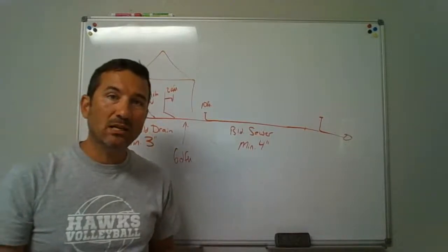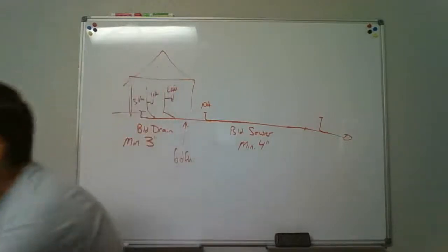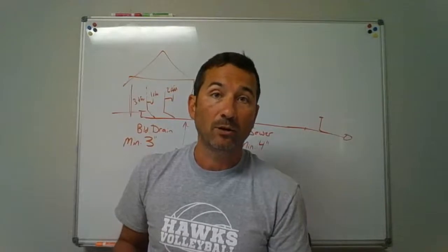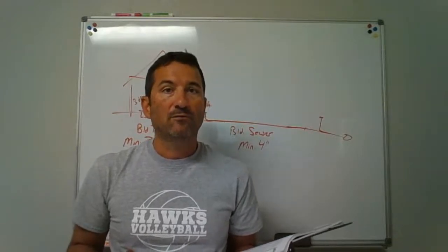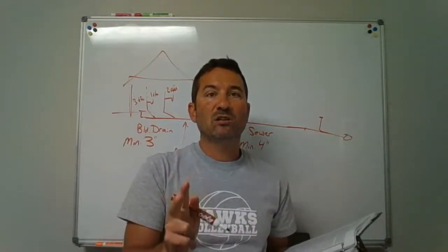The next note says a minimum of 2-inch diameter for this run underground. So if you were doing a house and it was on a slab, so anything that you're going to bury and it's going to be under the house. So maybe if you look back over here on page 67, it tells me if I'm running a tub, I could put a 1.5-inch drain. Yes, if it's on a crawl space where it's not underground. But if you're burying the line to go underground to go for that tub, that footnote says a minimum of a 2-inch line that's underground, okay?